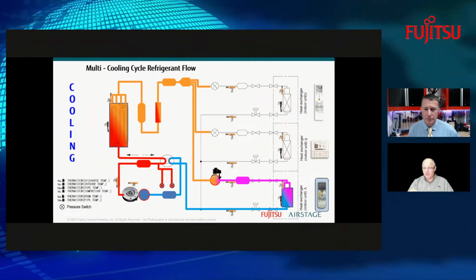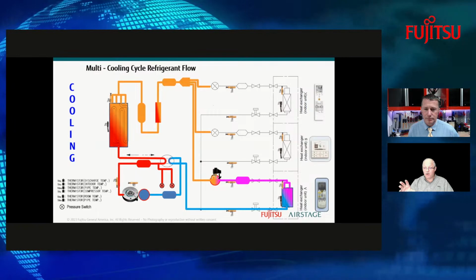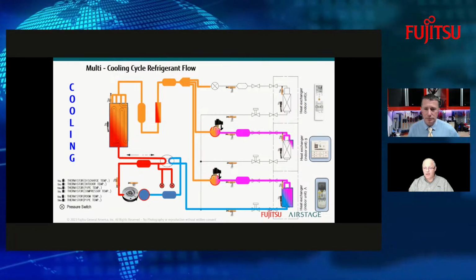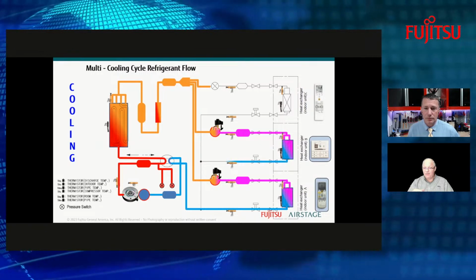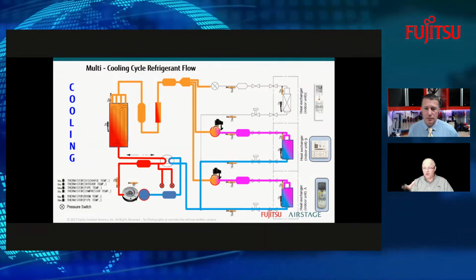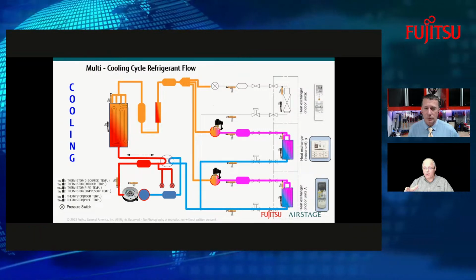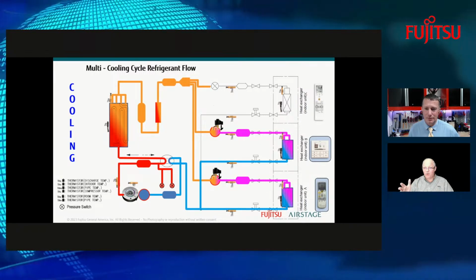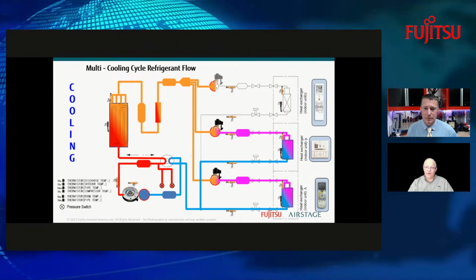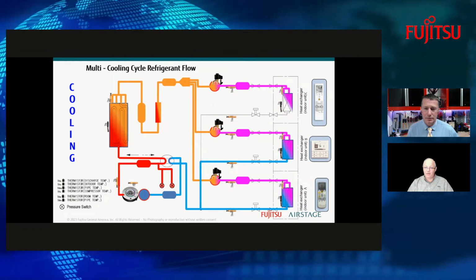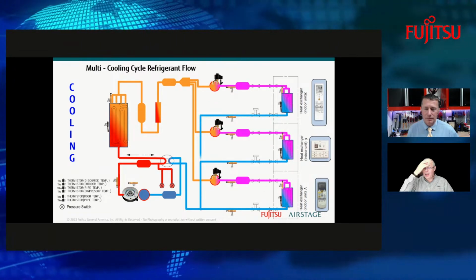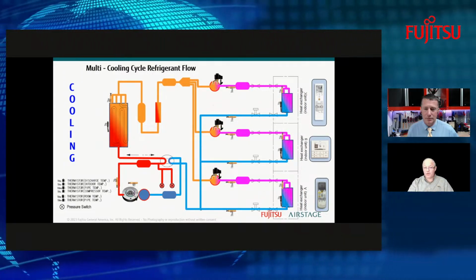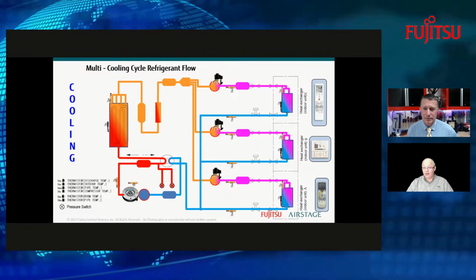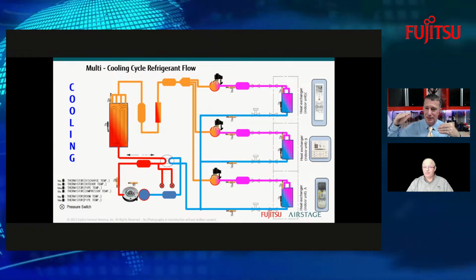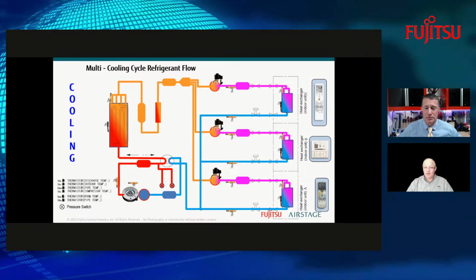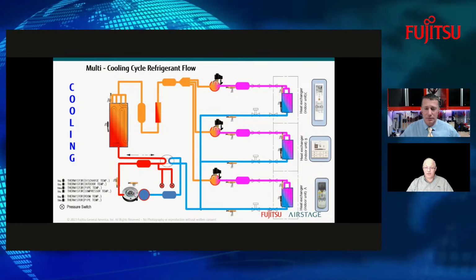But now the summertime gets even warmer. Now a second zone calls. The first zone is calling, and now the second indoor head calls. So the EEV just opens up and the indoor fan starts to turn. Now I've got two of my indoor units running, and still have one that's not. Well, finally, let's say it's really super hot out and everything needs to be running. Then the indoor EEV opens up and my third indoor unit becomes active. And you can tell as I bring each one of these on, that compressor and that outdoor fan motor are going to have to speed up to get rid of the heat. So it's good. The outdoor unit is going to change its capacity based on the load coming back from the indoor units. Yes, and that is remarkable brains for technology.